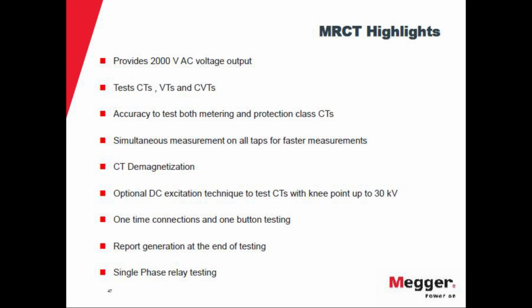As I mentioned, it's a one-time connection and one-button testing. You connect everything, and it runs all of the tests that I mentioned: insulation, winding resistance, demagnetization, saturation, and ratio and polarity. With one single run, one single button, you don't need to do anything else after you press the button. And it will generate a report at the end of the testing. So once you're done with the test, it also generates the PowerDB result.